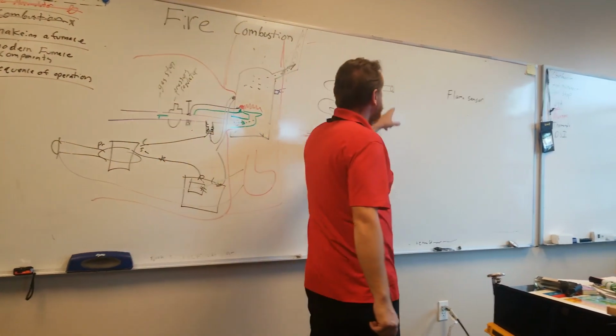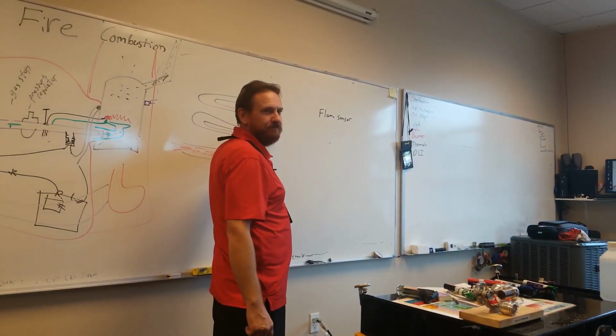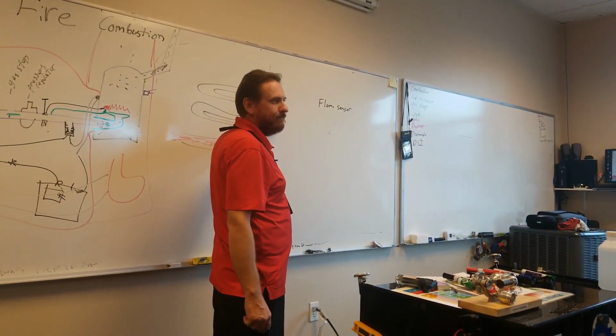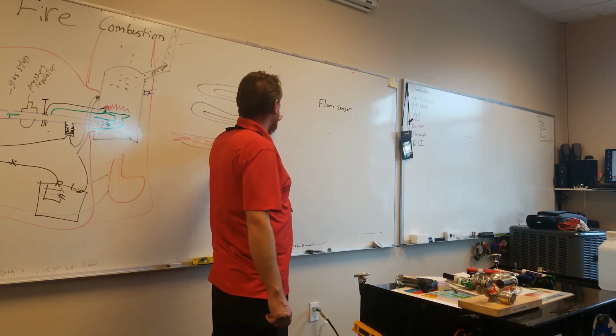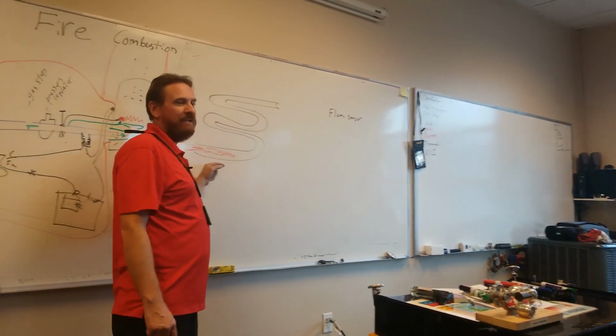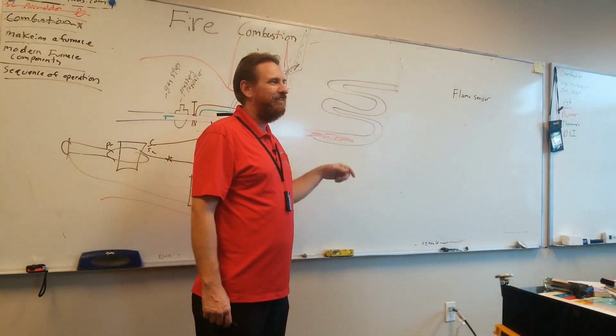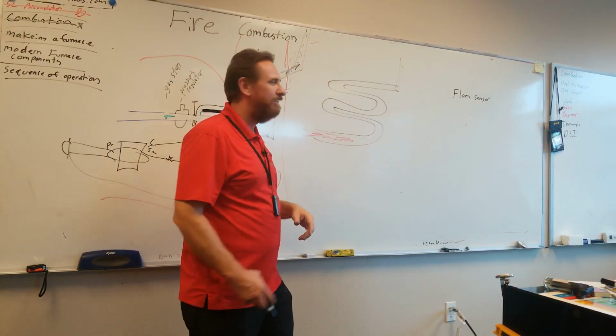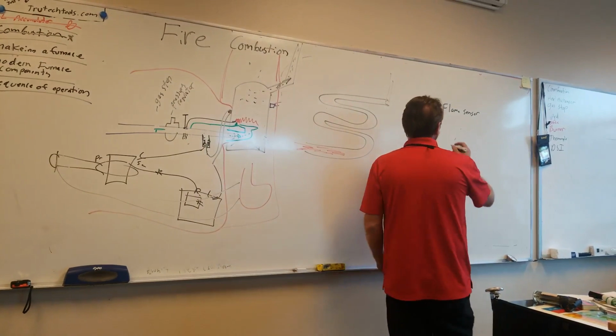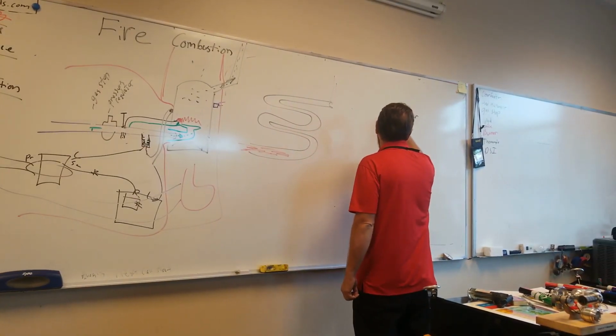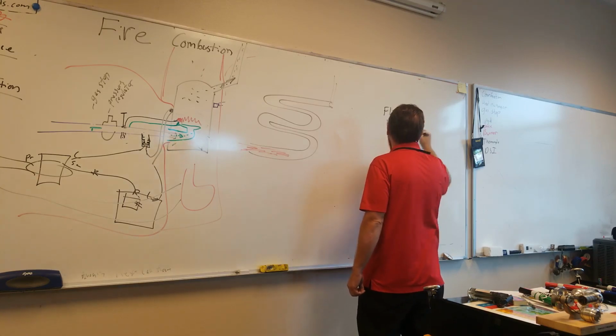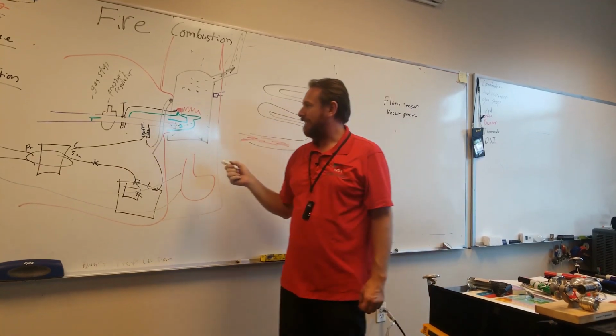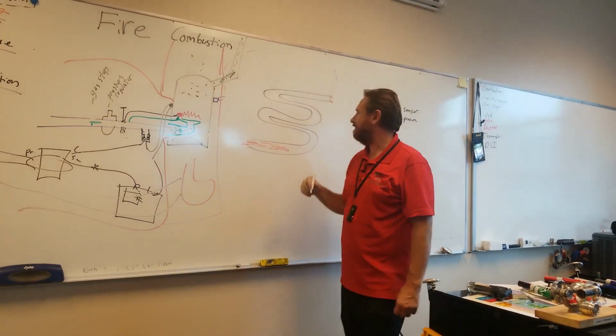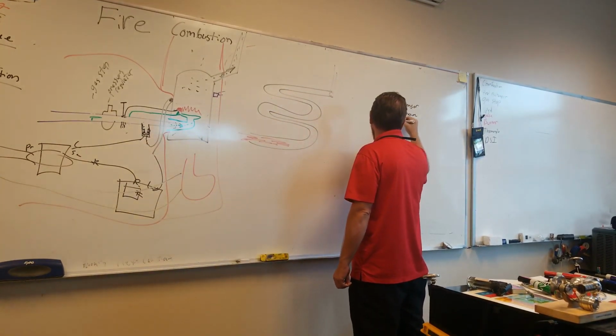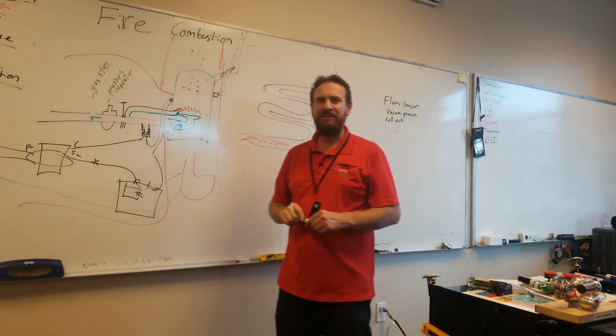And then, what if this motor right here stopped working? You won't get any heat. Well, if that motor stopped working and I sent gas and fuel at an angle, but there's nothing pulling it through, there'd be a fire rolling out, wouldn't there? So we're going to need some kind of a safety, which is going to be a vacuum pressure switch. And we're also going to need a rollout switch. So if the flame rolled out, we could shut stuff off for protection.